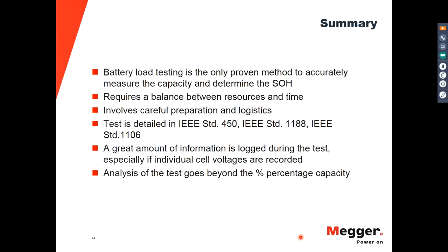So this is pretty much all the material we wanted to show today. As a summary, the battery load testing is the only proven method to accurately measure the capacity and determine the state of health of the battery. You need a lot of balance between the resource and time for the test, and again, it can turn into a cumbersome and complicated test if you are not well prepared.